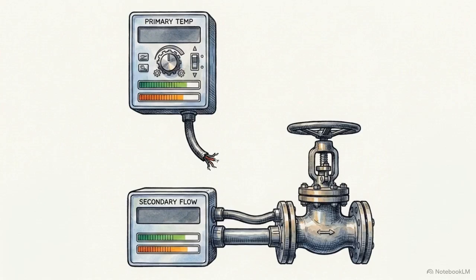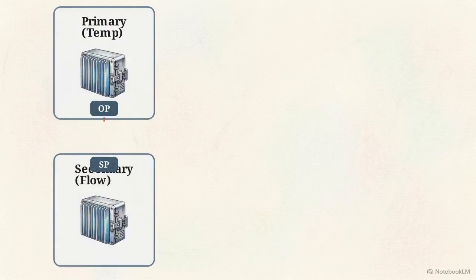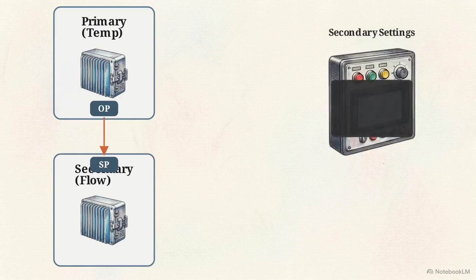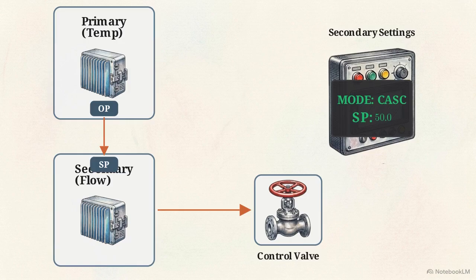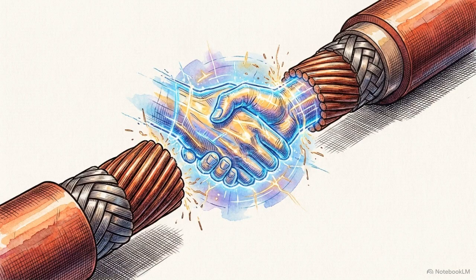But adding a second controller creates a hierarchy problem. The primary temperature controller can no longer communicate directly with the steam valve. The controllers must talk. The primary's output, its OP, becomes the secondary's live set point. But wiring isn't enough. The secondary controller can't stay in auto mode, which waits for human input. It must switch to cascade, or CASC, to accept the primary signals. You can run all the copper wire you want, but without that digital handshake in cascade mode, the two loops are completely disconnected. Let's test this logic.